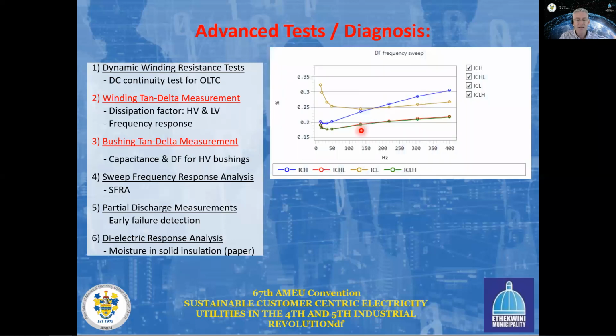And what we see from that is that, firstly, at 50 Hertz, the actual dissipation or the tan delta measurement should be, the CIGRE Guide 445 again specifies, less than 0.5% for a healthy transformer, or at least less than 1% is still acceptable. Above 1%, we can fail that transformer.